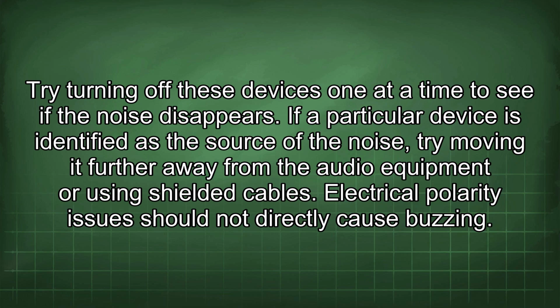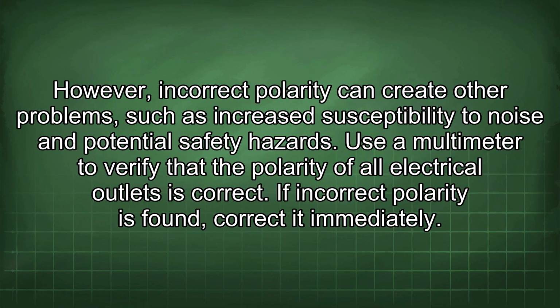Electrical polarity issues should not directly cause buzzing. However, incorrect polarity can create other problems, such as increased susceptibility to noise and potential safety hazards. Use a multimeter to verify that the polarity of all electrical outlets is correct. If incorrect polarity is found, correct it immediately.